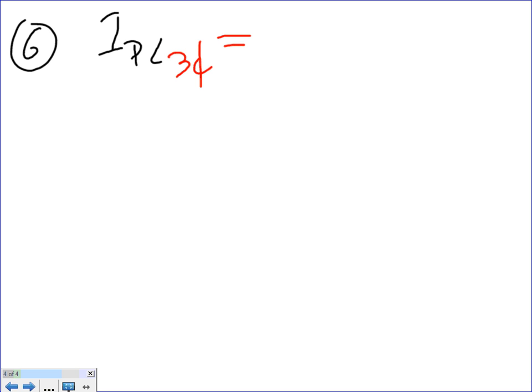Number 6, guys, is we need to find I primary line. The only thing we're going to add for I primary line, we're going to add two things: I primary line 3-phase. Can you guys add the words I primary line 3-phase? I'm adding this because there's line coming from the 3-phase and line coming from a single phase. I primary line 3-phase - this is piece of cake. What was the KVA of the 3-phase transformer? Divide by what's the voltage on the I primary line 3-phase? So what's the voltage, guys, on the primary side?